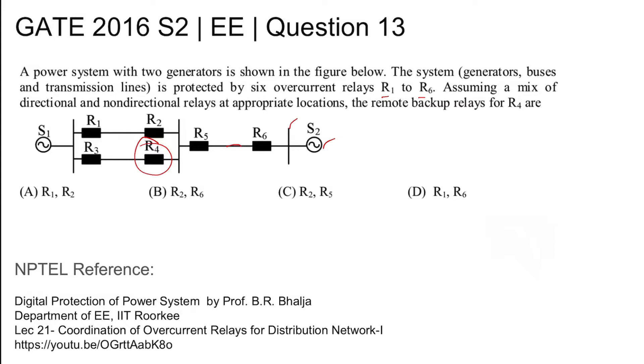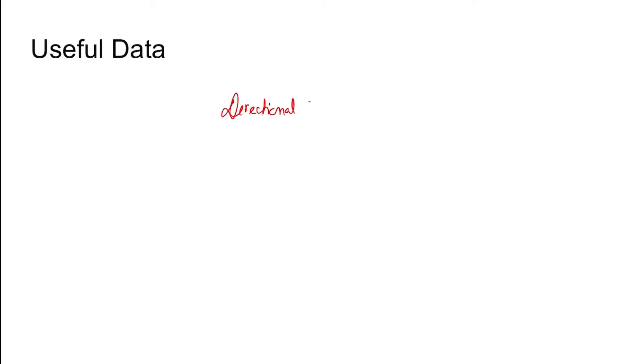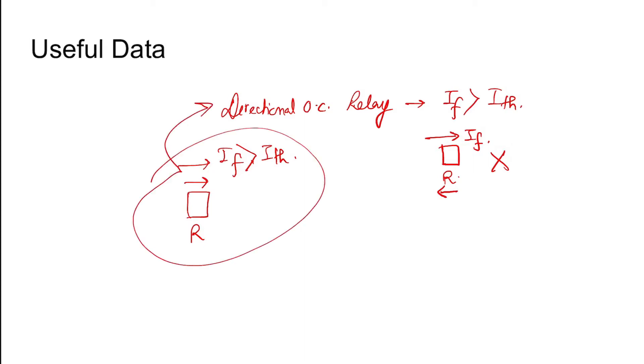The property of a directional overcurrent relay is that the fault current must be greater than the threshold current and must be in a particular direction. For example, if this is the fault current through this relay and the relay direction is this, then the relay will not operate. The relay will operate only if the direction of the fault current matches the direction of the directional overcurrent relay and is greater than the threshold value. So this is the working principle of a directional overcurrent relay.